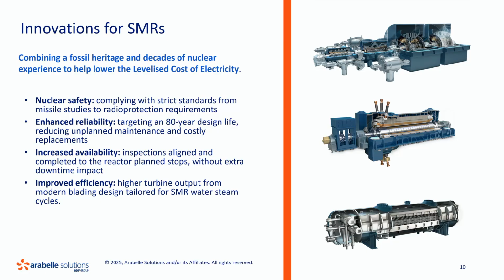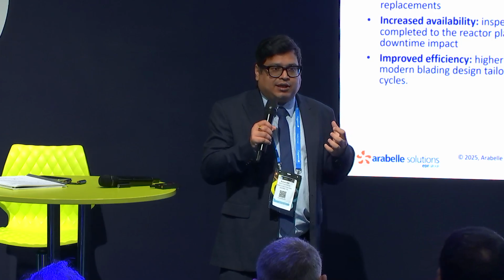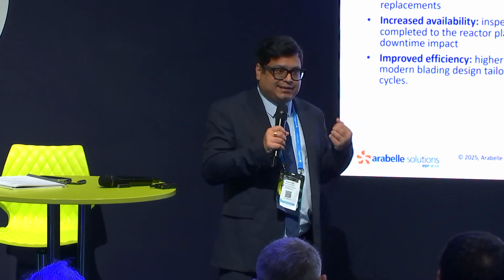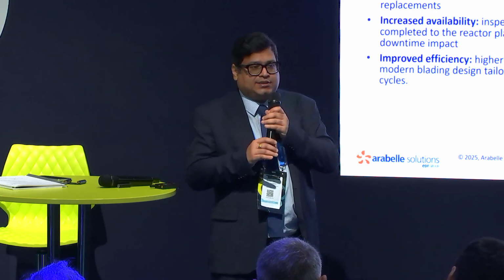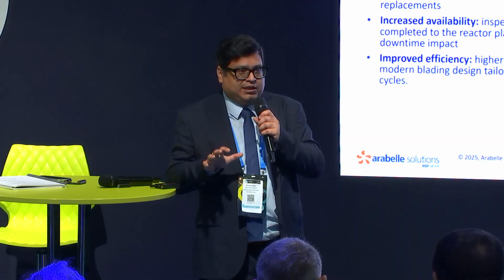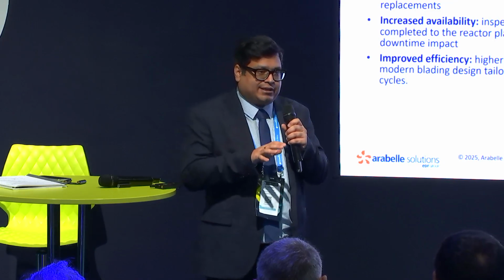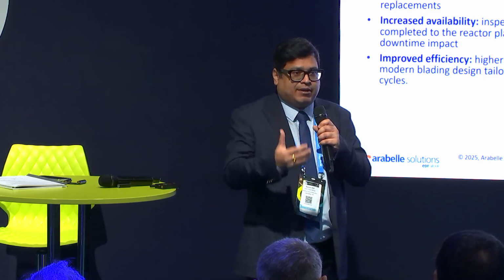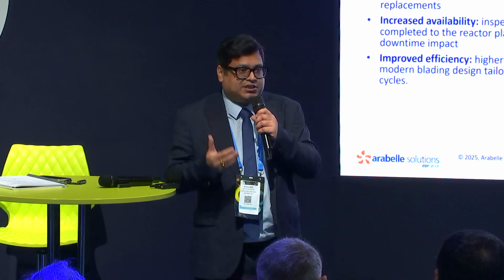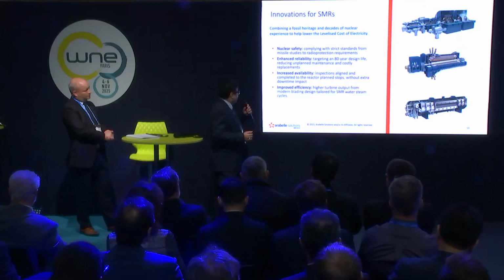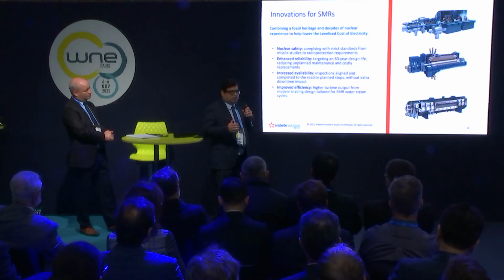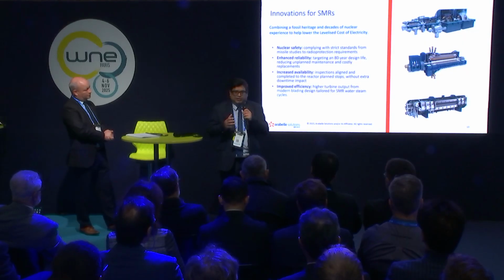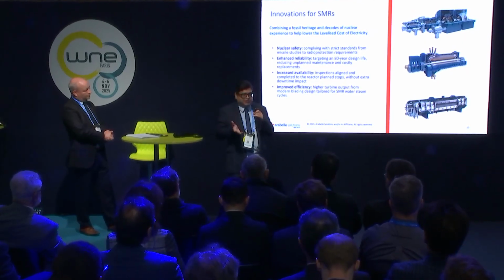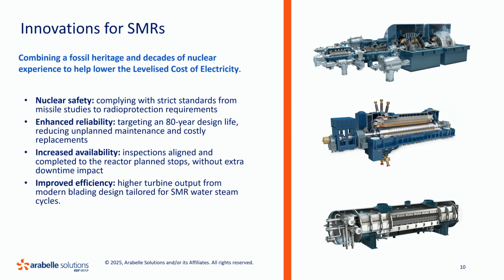The third is availability. It's quite important. Our large fleet Arabelle has an exceptional reliability record, so we want to bring that, and also synchronize the maintenance cycle of the steam turbine with the refueling cycle of the reactor, so it gets maximum availability and the steam turbine doesn't need additional maintenance. Then it's improved efficiency. We take the 3D blading technology and aerodynamic optimization from the fossil line and incorporate it into this, so it gets maximum efficiency at that level.